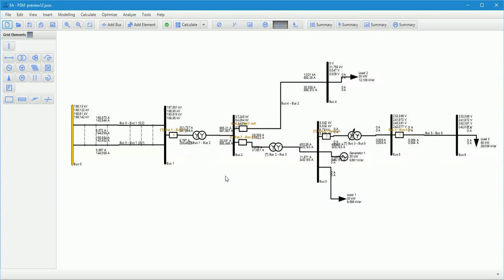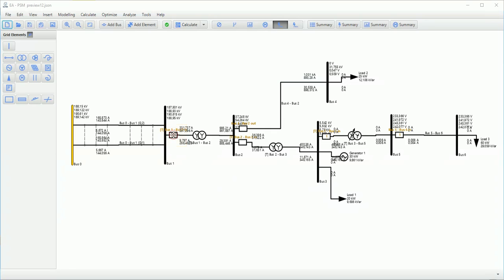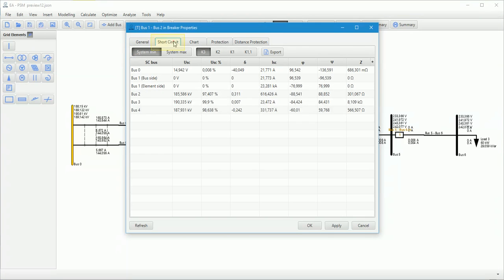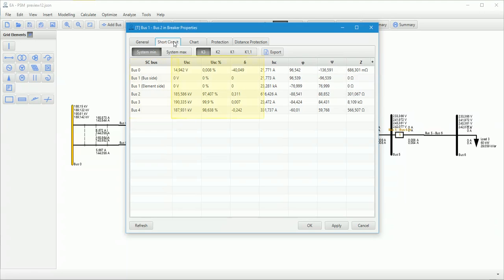In protection device properties, short circuit section, user can find all results which are essential for this device. In symmetrical short circuit, fault buses, voltages and its angle, current and its angle, and also impedance from protection device to the fault place and its angle are displayed.